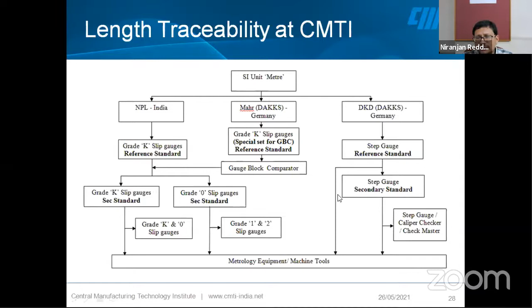In the sense, whenever you want the instrument to be used, it should be calibrated. When you have it calibrated, you need to ensure you get it calibrated from an accredited laboratory. In India, there is a board called NABL, National Accreditation Board for Testing and Calibration Laboratories, which gives the accreditation to the laboratories based on ISO IEC 17025. By this you can ensure the traceability of measurements in all your fields as such.